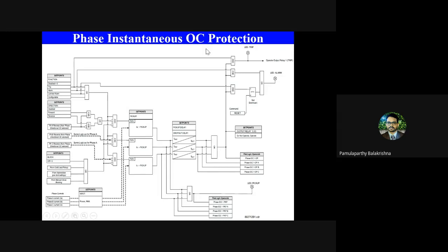Apart from that, there can be certain cases where I do not want this phase instantaneous overcurrent to operate. Such conditions can be like a cold load pickup. I don't know if you have heard about this cold load pickup condition. What it means is, when you have a distribution circuit which has been switched off for a long interval of time, the distribution circuit is supplying power to downstream transformers and various loads, including motors, capacitor banks, or whatever it may be.